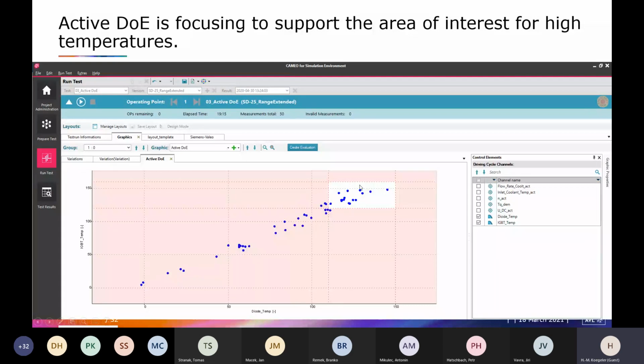So we targeted this range above 120 up to 160, and got some points there, obtaining a reliable model of the error at least for these two temperatures of the diode and the IGBT — a semi-physical model implemented in the inverter that needed to be validated on the test bed.